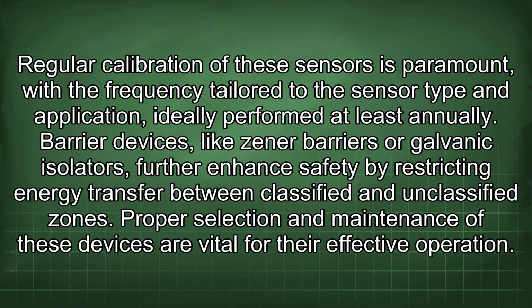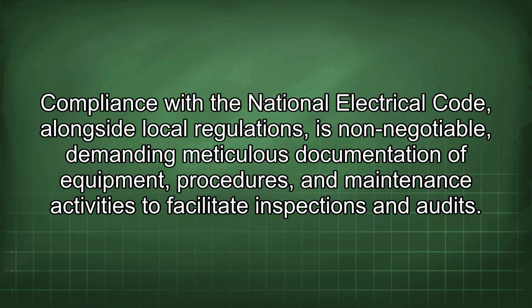Regular calibration of these sensors is paramount, with the frequency tailored to the sensor type and application, ideally performed at least annually. Barrier devices, like Zener barriers or galvanic isolators, further enhance safety by restricting energy transfer between classified and unclassified zones. Proper selection and maintenance of these devices are vital for their effective operation. Compliance with the National Electrical Code, alongside local regulations, is non-negotiable, demanding meticulous documentation of equipment, procedures, and maintenance activities to facilitate inspections and audits.